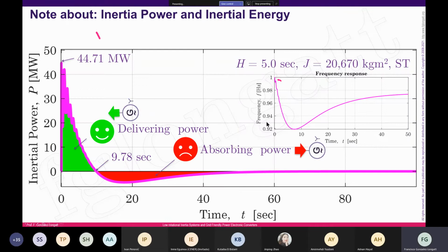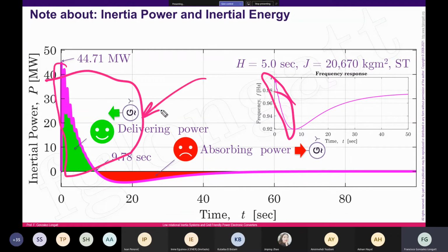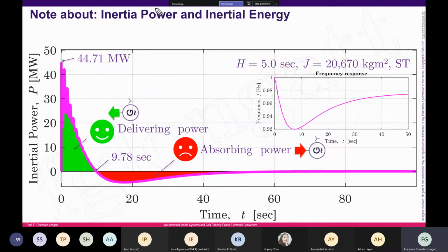Okay, when the ROCOF is going in this direction, when the frequency is going down, okay, no problem. We have inertia contribution and the synchronous machine produces energy and delivers energy to the system. But when the frequency is recovering, you have this other area over here. And that is when the machine tries to reestablish the energy balance in the rotor, and it's absorbing power. What I'm trying to tell you is that one of the issues related with the natural inertial response of a synchronous machine is that this response is basically dominated by the ROCOF. And depending on that ROCOF, you can have the problem that during the recovering period, you have consumption, okay?